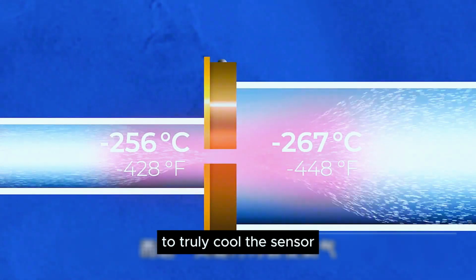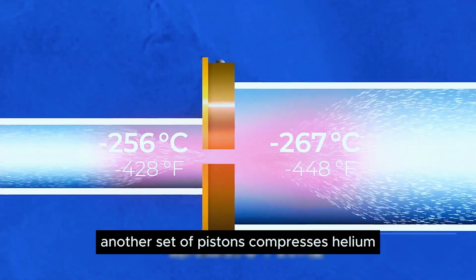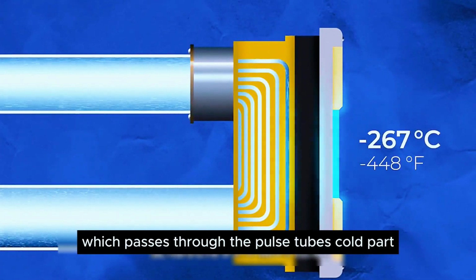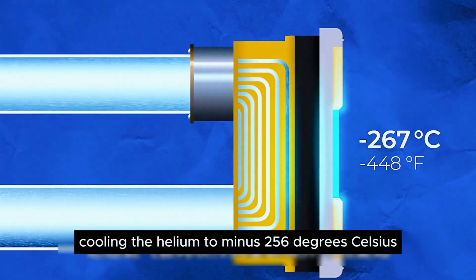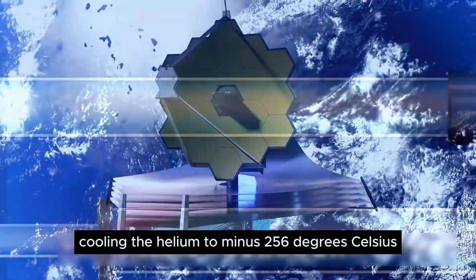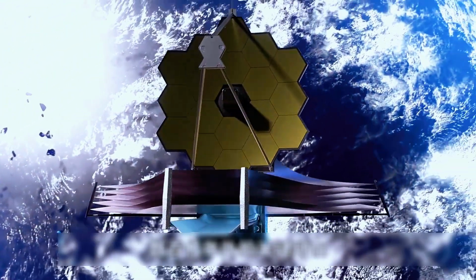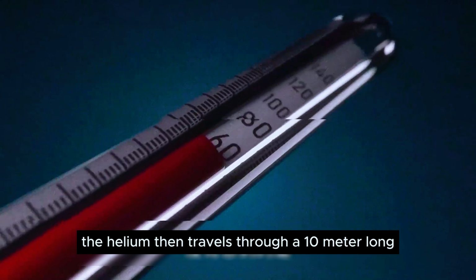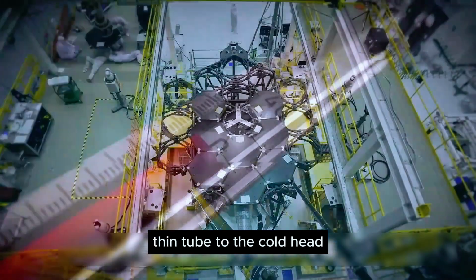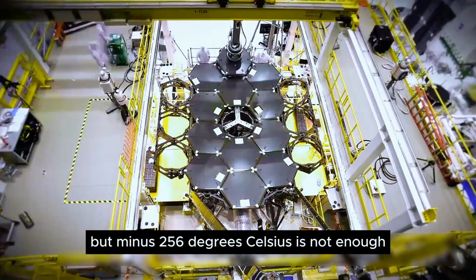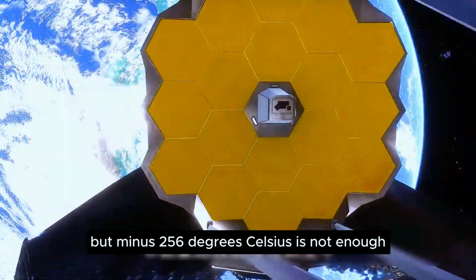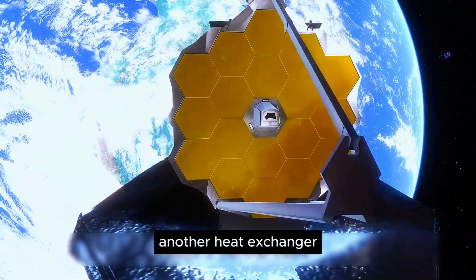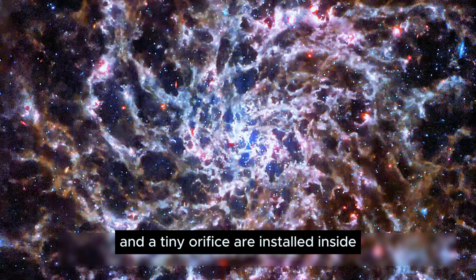To truly cool the sensor, another set of pistons compresses helium in an independent circuit, which passes through the pulse tube's cold part, cooling the helium to -256 degrees Celsius. The helium then travels through a 10-meter-long thin tube to the cold head, but minus 256 degrees Celsius is not enough. Another heat exchanger and a tiny orifice are installed inside.